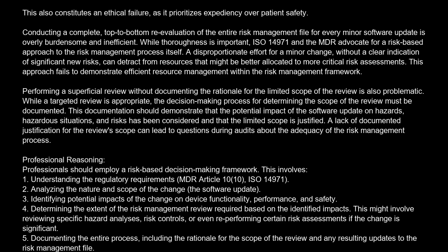Professional reasoning. Professionals should employ a risk-based decision-making framework. This involves: 1. Understanding the regulatory requirements, MDR Article 10.10, ISO 14971. 2. Analyzing the nature and scope of the change, the software update. 3. Identifying potential impacts of the change on device functionality, performance, and safety. 4. Determining the extent of the risk management review required based on the identified impacts.